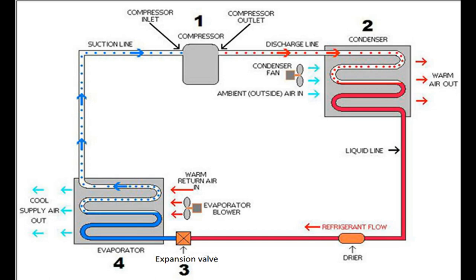The compressor converts this gas into high pressure, high temperature vapour refrigerant, and it goes into the condenser through the discharge line. In the condenser, high pressure, high temperature vapour refrigerant enters through the discharge line. Latent heat is rejected to the atmospheric air from the vapour refrigerant, and it converts into liquid refrigerant without changing its sensible heat. This high pressure, high temperature liquid refrigerant then goes to the expansion valve through the liquid line.